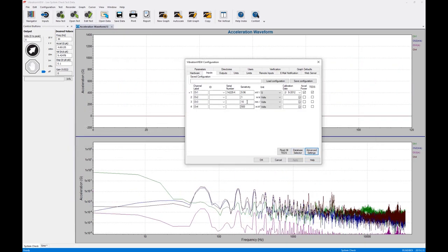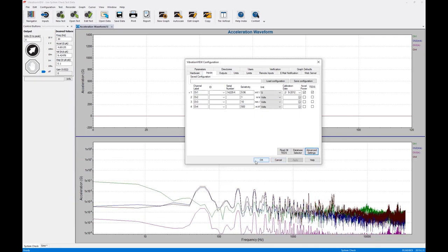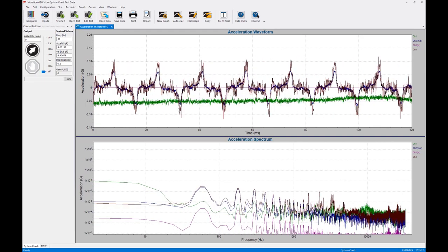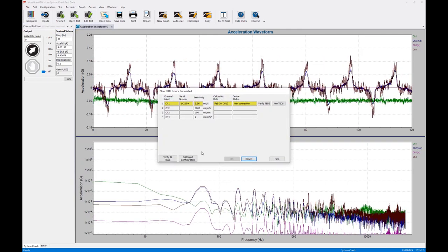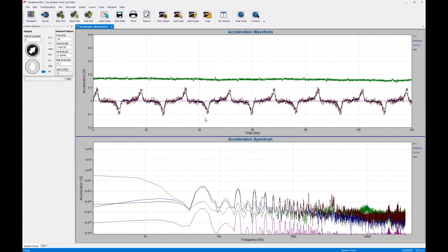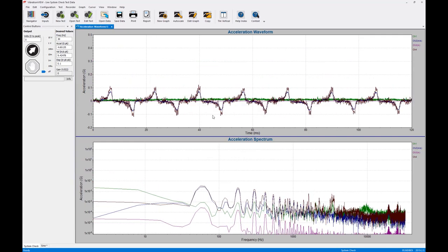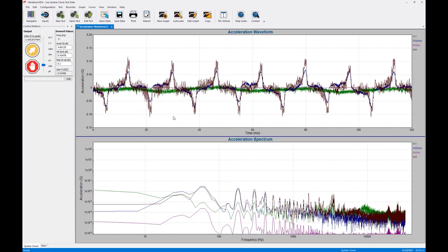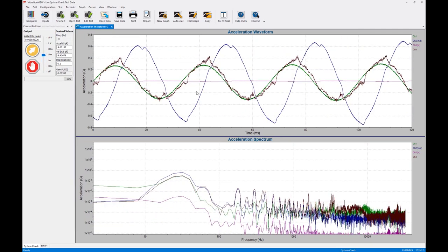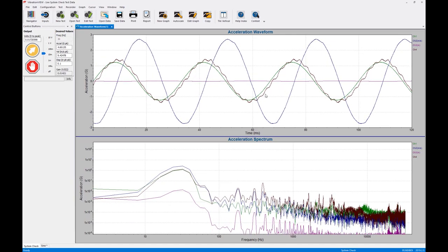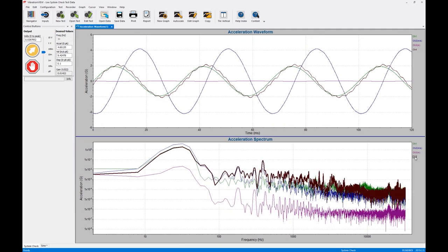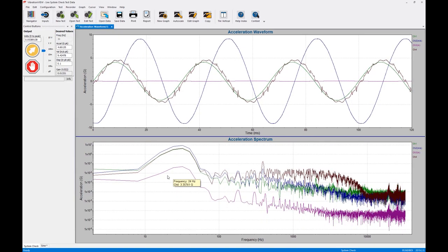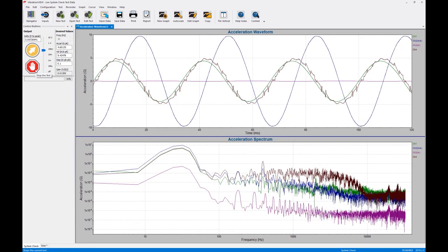I can save that, and you can see that my meters per second, millimeters per volt, and meters per second squared per volt are all saved. Now, I can run a quick system check to make sure that I have everything configured appropriately. Should start seeing motion on my shaker, and I can see that I am getting signal through all of my channels. If I look at my spectral density here, or my FFT, I can see that I am getting feedback and my sensors are configured appropriately. All right.